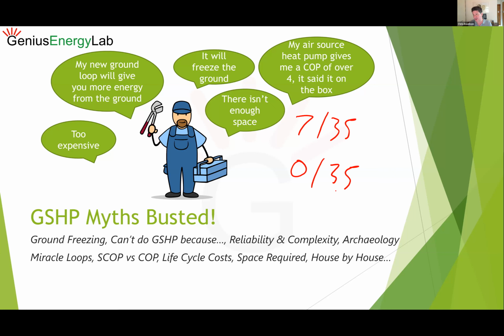Ground source, if you just do a straight rating point comparison, is going to come out less well than air source in some cases. So you absolutely must use a seasonal COP, which is the annual heat delivered divided by the annual electricity consumed. And that's a much fairer comparison.